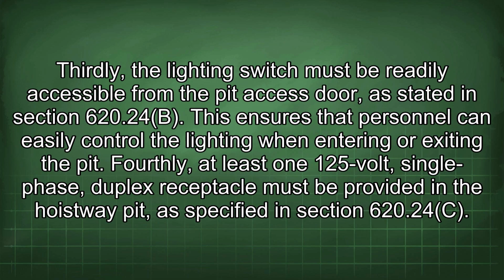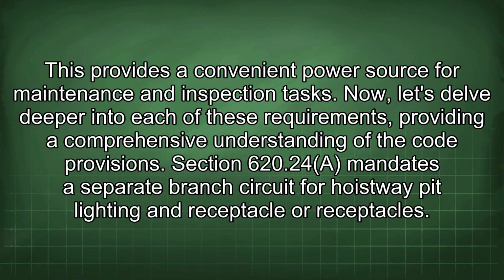Thirdly, the lighting switch must be readily accessible from the pit access door, as stated in Section 620.24b. This ensures that personnel can easily control the lighting when entering or exiting the pit. Fourthly, at least one 125-volt single-phase duplex receptacle must be provided in the hoistway pit, as specified in Section 620.24c. This provides a convenient power source for maintenance and inspection tasks. Now let's delve deeper into each of these requirements, providing a comprehensive understanding of the code provisions.